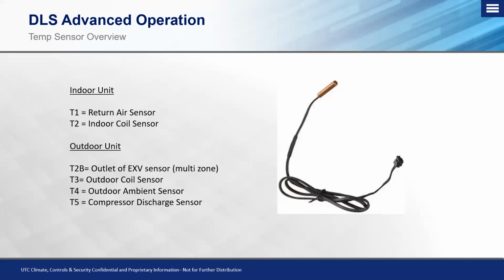And then finally, on the multi-zone style systems, we have a T2B sensor, and this is on the outlet of the EXV. Essentially, what this T2B sensor does is it takes an average between, depending on how many zones you have that are actively running, and generates a target temperature, which in turn will control a specific position or a minimum position of that EXV. Okay, we'll get into that in a minute, and how that affects oil return and also the minimum position by using that T2B sensor on the multi-zone style systems.